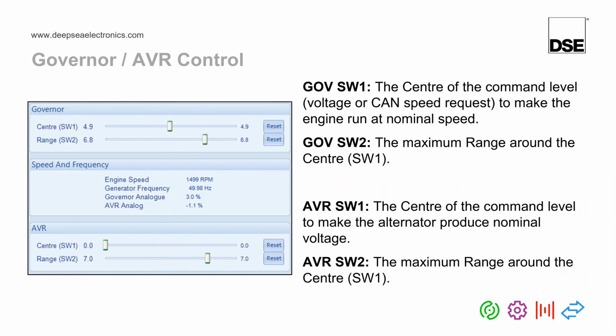Effectively, you're only governed by the amount of voltage that you require. As an example, if you require 4 volts for nominal and 8 volts to run at maximum RPM, then as long as you can adjust your slider to achieve that, it shouldn't be an issue. So if the DeepSea module has to produce the full 10 volts to allow you to gain 8 volts at the other end of the wiring, then it shouldn't be a problem.